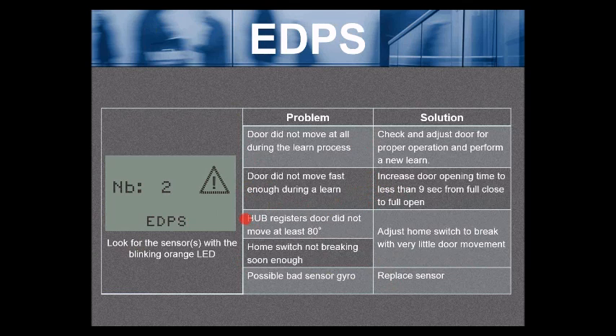Next most common error is the hub registers the door did not move at least 80 degrees. You need to adjust the home switch to break with very little door movement. I'll speak more on that in just a second.